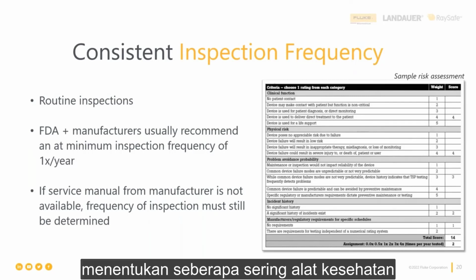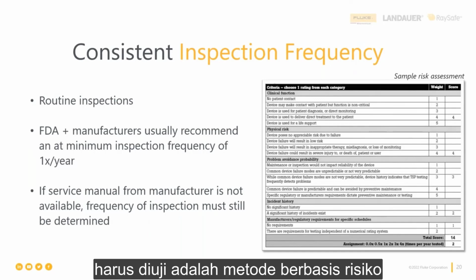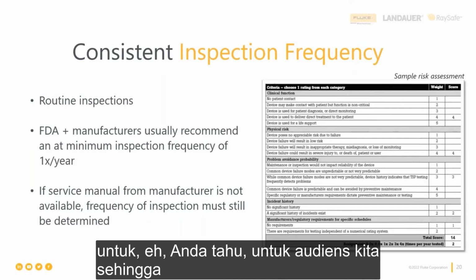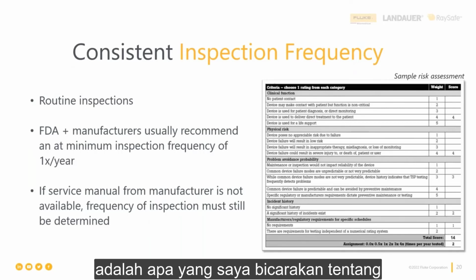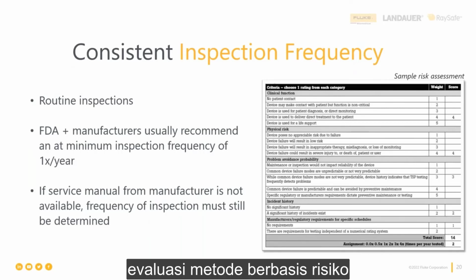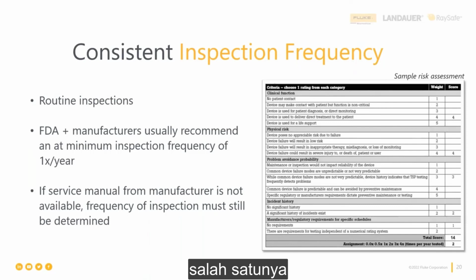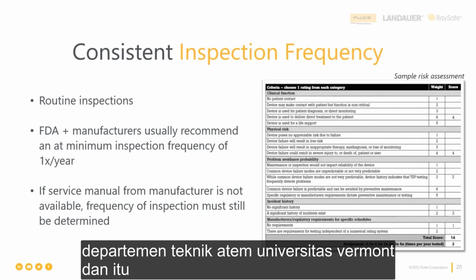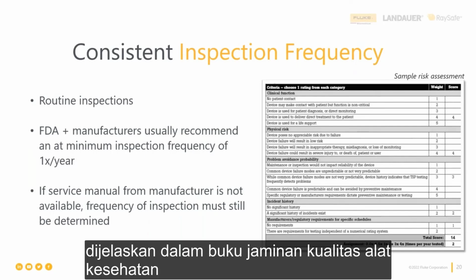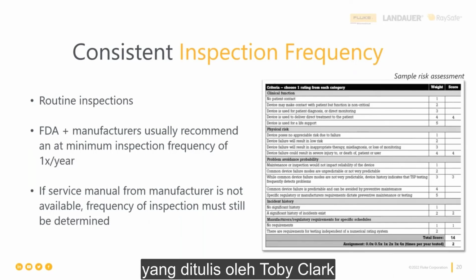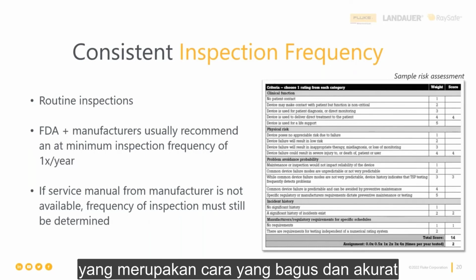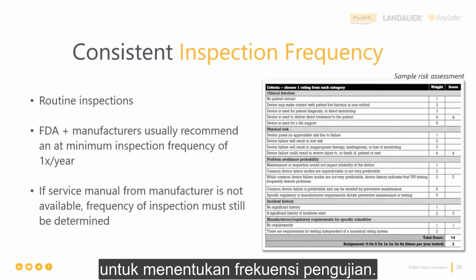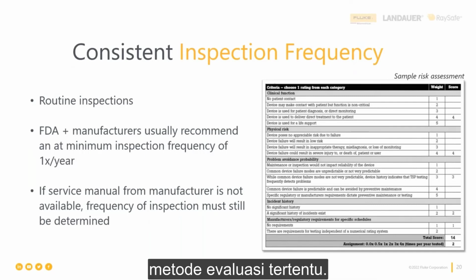So a great method for determining how often a medical device should be tested is a risk-based method. This is what we typically recommend to our audiences. The example that you can see on this slide is exactly what I'm talking about, that risk-based method, that evaluation that helps you determine that frequency of test. This particular one is done by the University of Vermont's Biomedical Engineering Department, and it is described in the Medical Equipment Quality Assurance book written by Toby Clark, which is a great and accurate way to determine the frequency of test. We very often get questions on how to get access to this book and to this particular evaluation method.